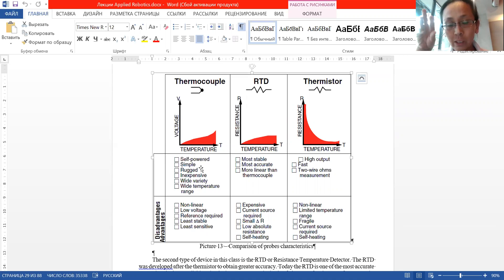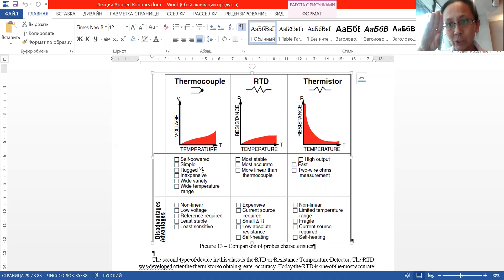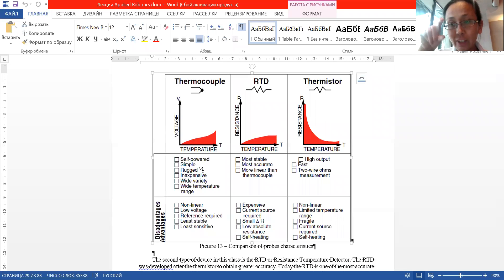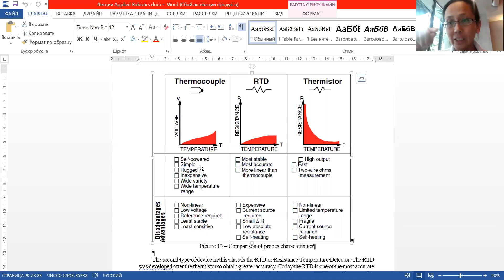For RTDs, the advantages are: most stable, most accurate, and very linear — you can see from the graph. The disadvantages are that they are expensive due to the platinum material, they need external power to operate since they don't generate their own signal but measure resistance, the resistance differences are small, the absolute resistance is also low, and they are self-heating which can impact measurements.